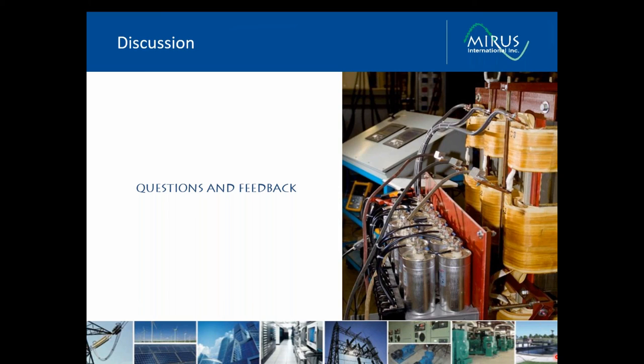With the Mirus Lineator, our designs are such that we are less than what the generator manufacturer's reactive power capability curves would be. So in normal operation, you wouldn't need to switch out the capacitors. But you might have multiple generators that operate in parallel, and you can have situations where you'll be shutting off the majority of the generators and maybe running on one generator, and you keep all of the filtered loads connected on the system. Then you could have a situation where the capacitive reactive power might exceed that of the generator. So if that's a possibility, we would recommend that contactors be included with the passive filter, with the capability of switching them out under light loads.